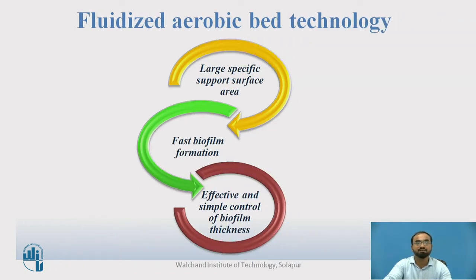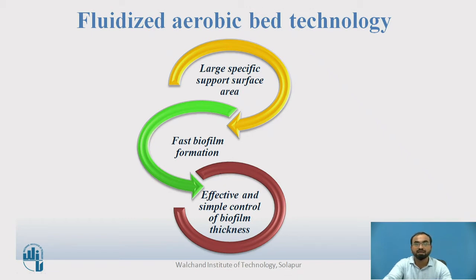The main point that makes this technology famous is that it always provides a large specific surface area, meaning the media has a higher surface area. Automatically, a fast biofilm can be formed on that media, similar to MBBR. There is effective and simple control on the biofilm — if the thickness increases, we can take out some media, clean it up, and add it back into the bed. So it is simpler to maintain as well.